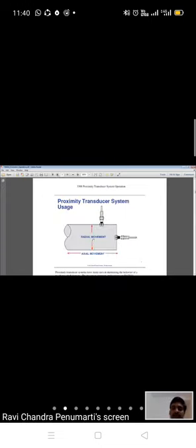Normally, as I explained in earlier slides, we measure radial vibration and axial vibration. Radial vibration is perpendicular to the axis. If this is the axis, this is the radial vibration, and axial vibration will be this one, parallel to the axis. Axial vibration is much more dangerous than radial vibration. Why? Because if our shaft itself is moving front and back, it will have a lot of unbalance and it will result in damage to the bearing of the machine itself. In both cases we use proximity probes only.